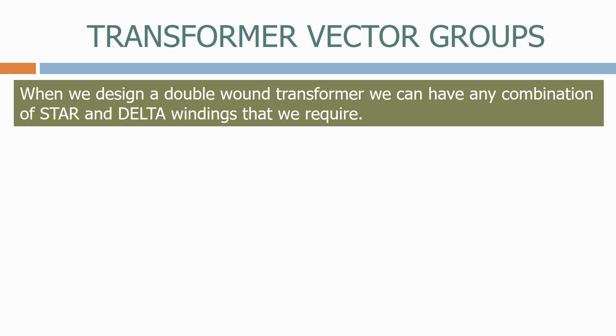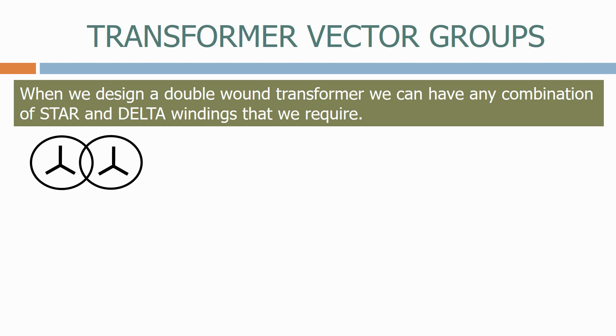When we design a double-wound transformer, we can have any combination of star and delta windings that we require. Here's a star-star transformer, with a star winding on the primary and a star winding on the secondary. A star-star transformer traditionally has a zero-degrees phase shift.